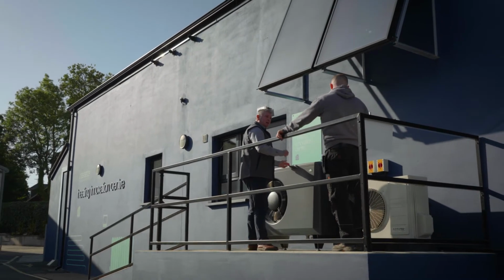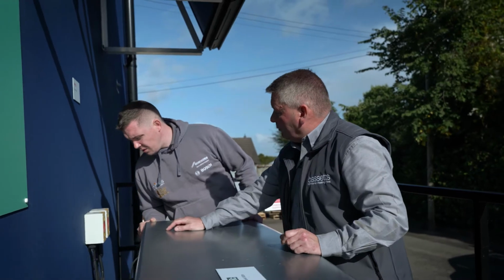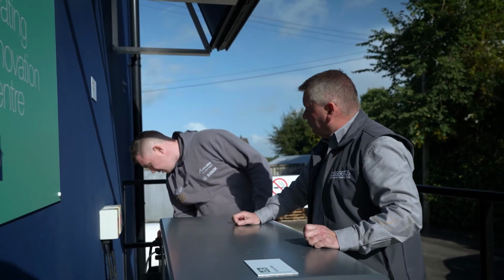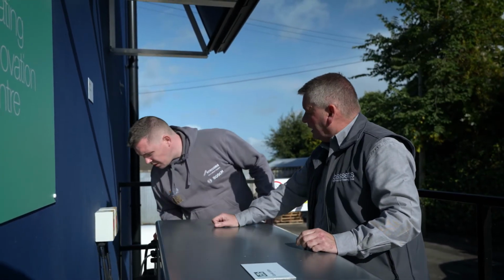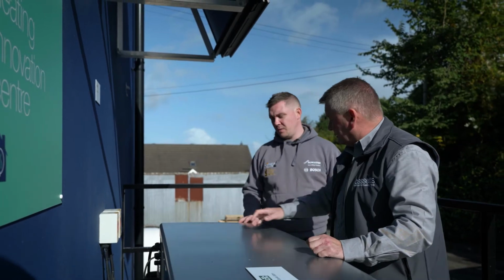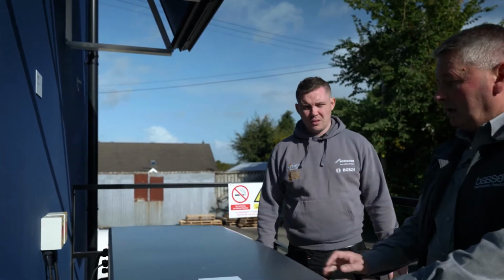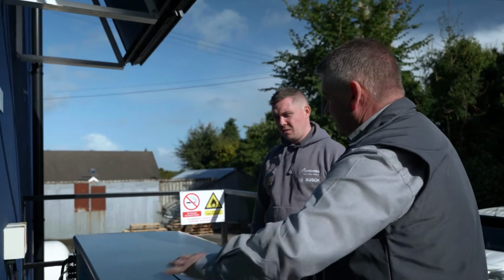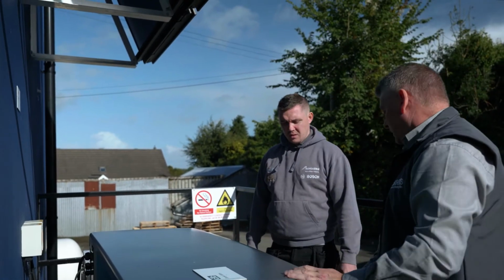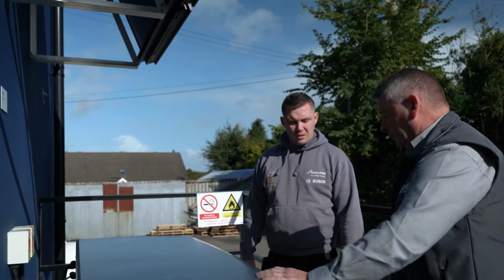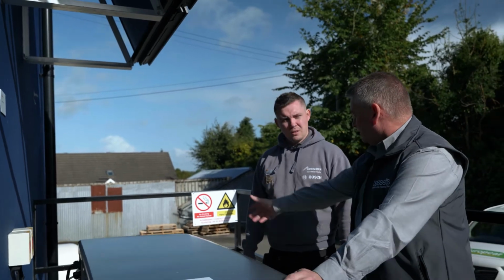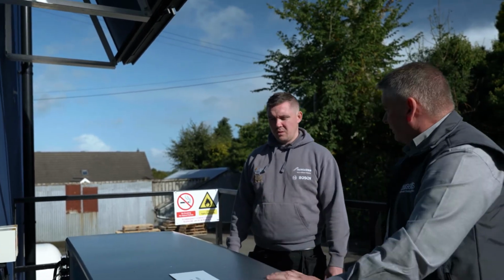They're both connected. When you see your flow and return come out, there'll be an isolating valve, and they're both connected by flexibles just to help with anti-vibration. They will both be approximately 400 off the wall just to get an air current through it. You're leaving approximately a metre to the front and about 400 each side. That's the clearance around the machine.